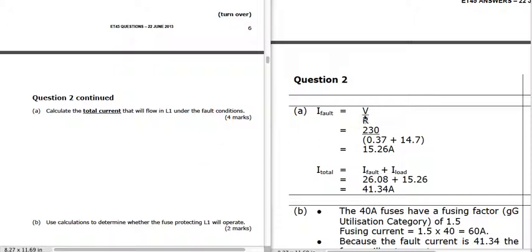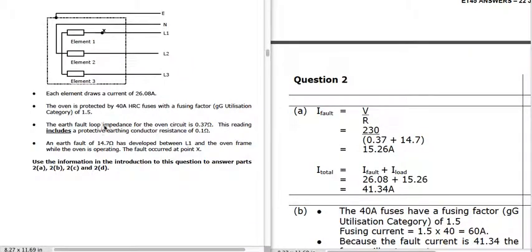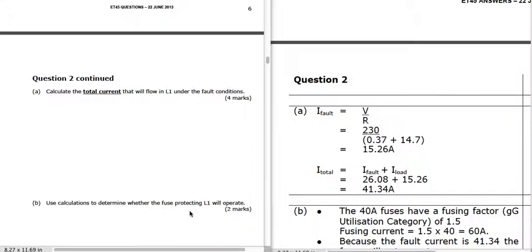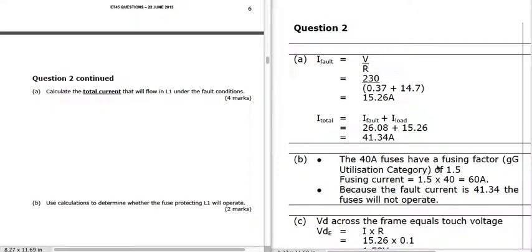The fault current is V over R using basic Ohm's law. This resistance is a combination of the 0.37 Ω earth fault loop impedance and the 14.7 Ω fault — those two added together divided into 230 gives us 15.26 amps. The total current is 15.26 plus the 26.08 amps that the element draws under normal load, giving a total current of just over 41 amps. Because of the fusing factor it takes at least 60 amps to blow that fuse, and our fault current is only just over 41 amps, so the fuse will not operate.